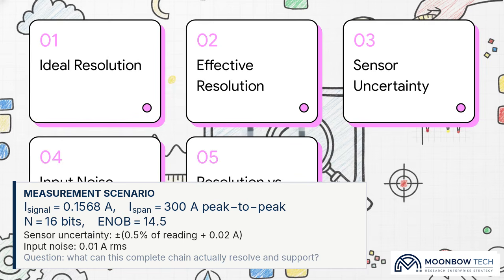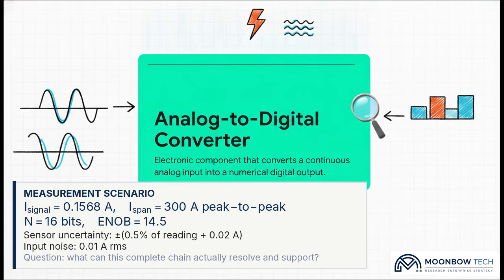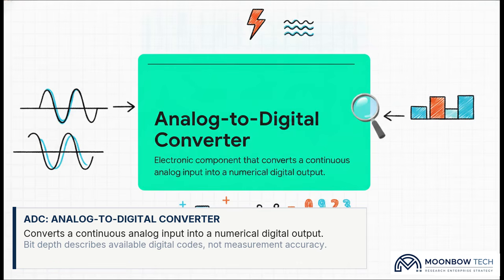We'll start with ideal resolution, move to effective resolution, factor in sensor uncertainty, introduce input noise, and wrap up with resolution versus accuracy. Before we jump into the math, let's just quickly lock in our terminology. An ADC, or analog to digital converter, is essentially the electronic heart of our instrument. It's the component that takes our continuous analog input, our physical real-world current, and chops it into a discrete, numerical digital output that a computer can actually process.